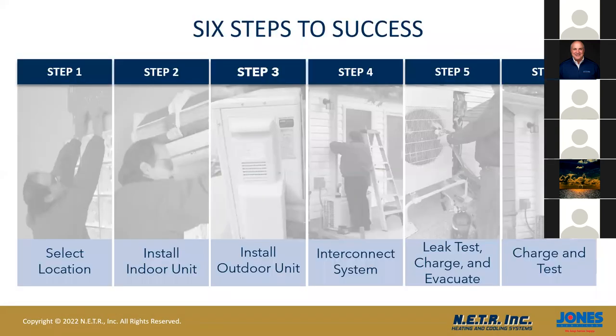All right, so let's look at the six-step process. This is based around a wall unit, but this could be a ducted unit. This could be anything. I just want to show you what happens: selecting locations, installing indoor units, installing outdoor units, interconnecting the system. I'm going to get into leak testing, charging and evacuating the lines, the refrigerant lines that would be installed, and the charging and the testing of what would need to be done.